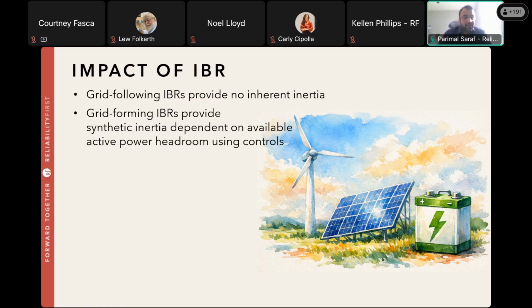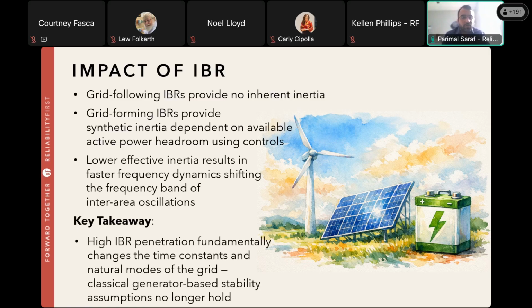So essentially what will happen is inertia has a major impact through how it's modeled in the state matrix and the small signal stability analysis. Inertia forms a major aspect of how it impacts the frequency band and damping of inter-area oscillations. So essentially, as we have more IBR penetration going forward, as a replacement of the inertia, it will have a significant impact on altering these inter-area modes through their damping and frequency bands. Next slide, Courtney.